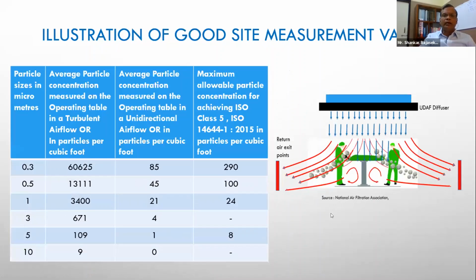And if you look at good values of site measurements, average particle concentrations measured on the operating table, that's the important phrase. The HTM is the only one of the three that we talked about. The HTM is the standard that talks about measurement of particle counts on the operating table.